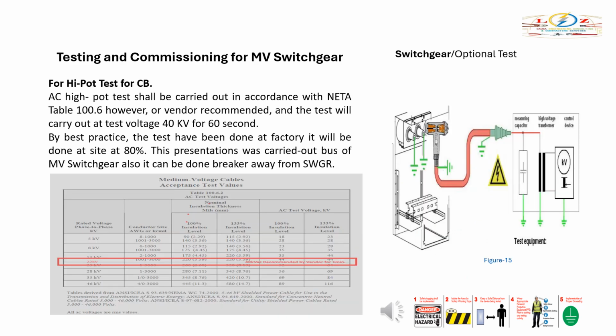For the high potential test for the circuit breaker, the AC high pot test shall be carried out in accordance with NETA Table 100.6, or as recommended by the vendor, and the test will be carried out at a test voltage of 40 kV for 60 seconds. By best practice, the test has been done at the factory; it will be done on site at 80%. This is also carried out on the bus of the MV switchgear in this setup, however it is also acceptable to conduct it with the CB drawn out, or isolated and away from the MV switchgear panel.